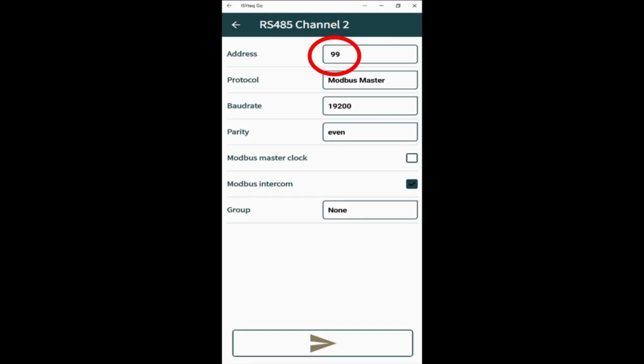Each of these boxes can be edited, but please be careful. Only experienced people should make changes to some of these. For example, if you change the baud rate, this is factory set and matches that set on the HMI. So if the controller baud rate is changed, so must also the HMI and any other devices on the same network.